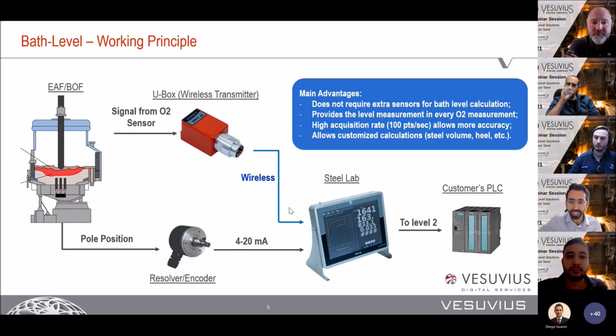Our steel lab is basically the heart of the system, receiving wirelessly the temperature, oxidation, and the position of the manipulator. This is processed, we get a bath level, and it's sent to the PLC for data purposes at the customer. What are the main advantages we can see right away?